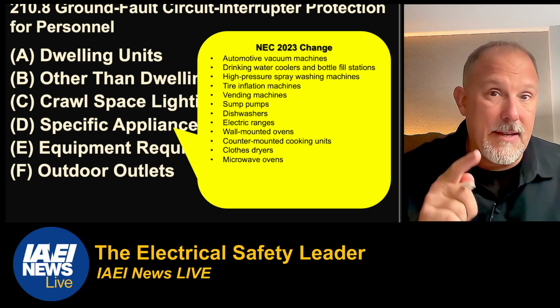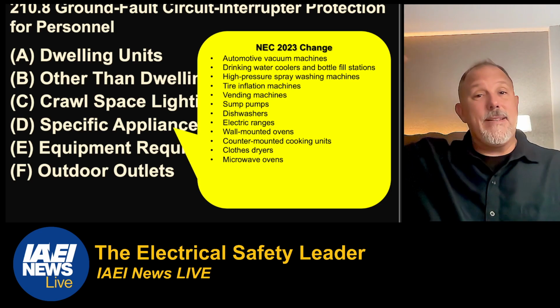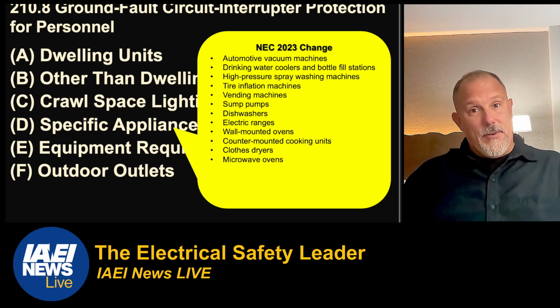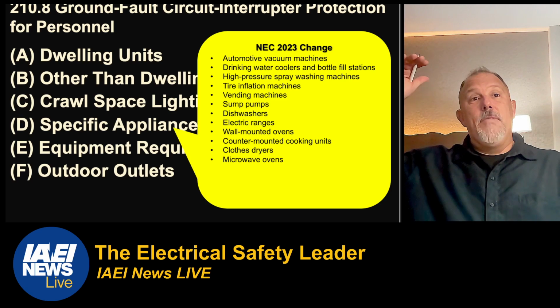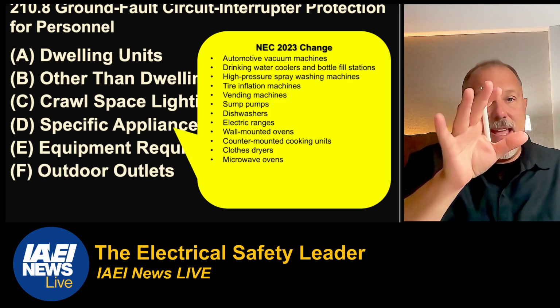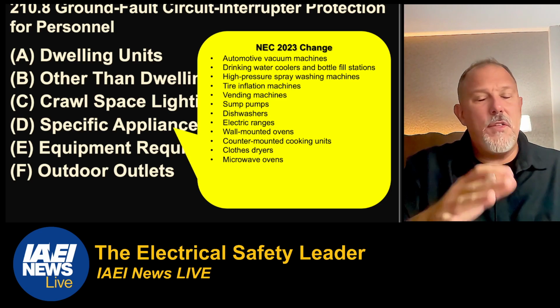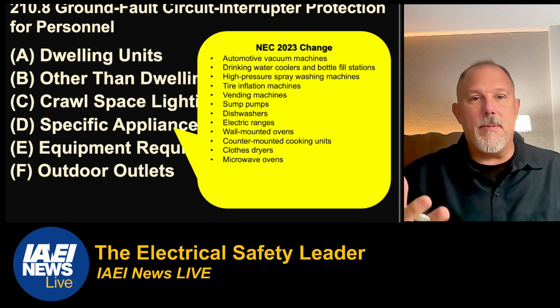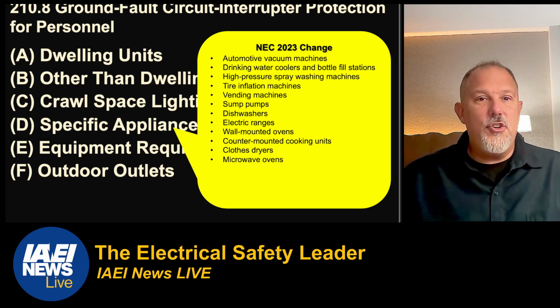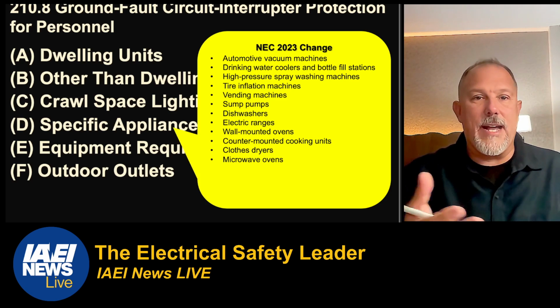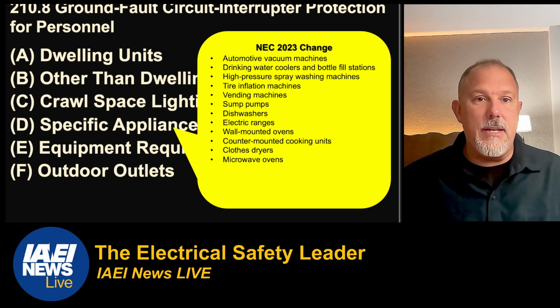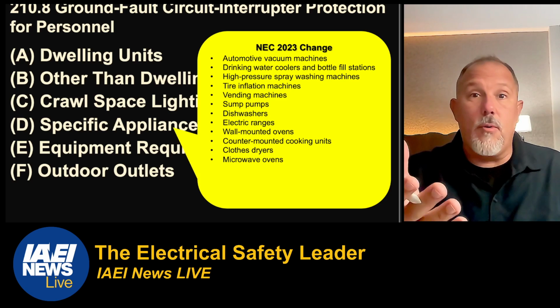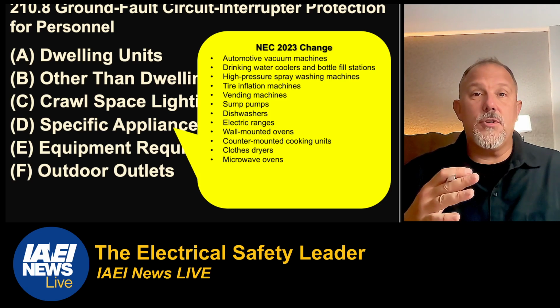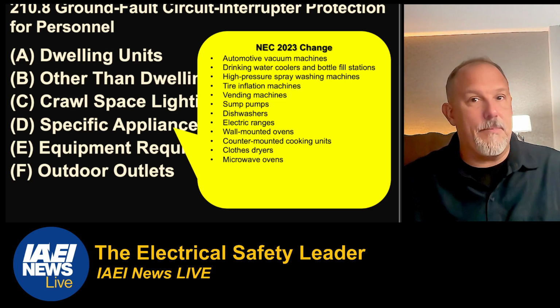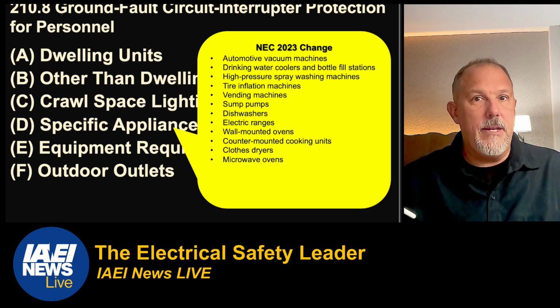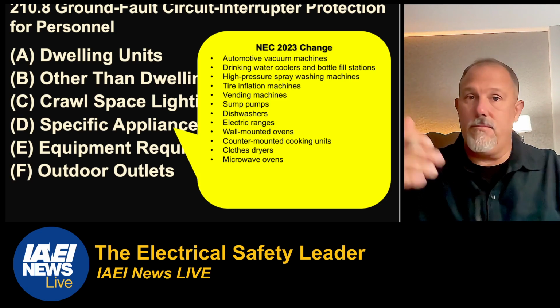Now, the other thing that this does, remember in that discussion earlier when I talked about other than dwelling units, that they're doing the measurement from the appliance. Think about a residential kitchen: you probably have an electric range. You might have a wall-mounted oven or a counter-mounted cooking unit, electric, obviously. Clothes dryers, definitely. Microwave ovens. Whether they're hardwired or receptacle, cord and plug connected. If they're cord and plug connected and they're in a kitchen, covered.